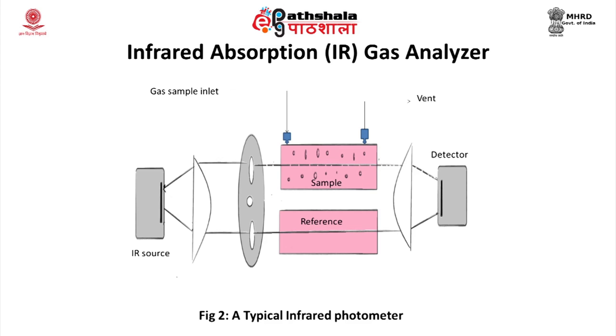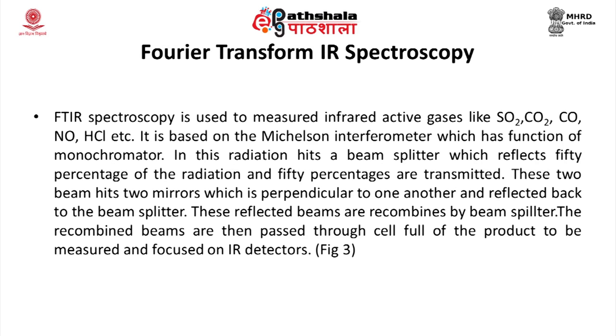Ultraviolet absorption: gases like nitrogen dioxide and sulfur dioxide absorb UV radiations. A major limitation of UV radiation is its high cost. Fourier Transform IR (FTIR) spectroscopy is used to measure infrared-active gases like SO2, CO2, CO, NO, and HCl. It is based upon the Michelson interferometer, which functions as a monochromator. In this setup, radiation hits a beam splitter which reflects 50% and transmits 50% of the radiation.